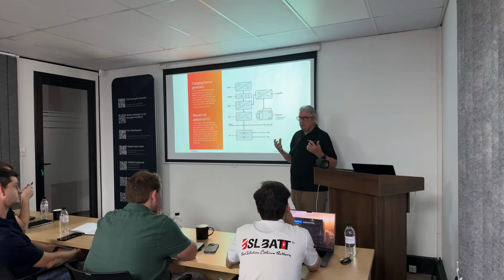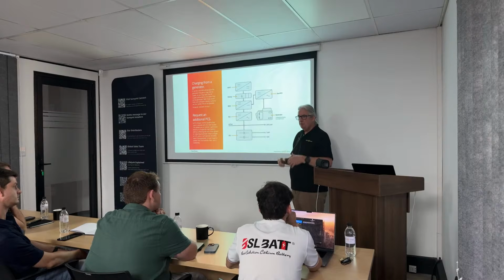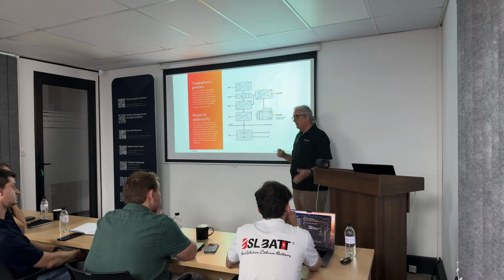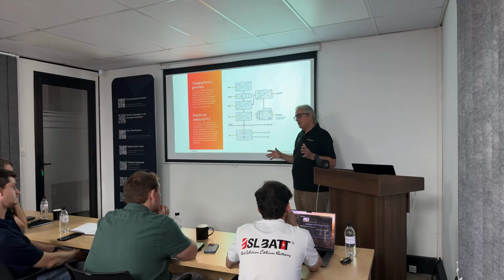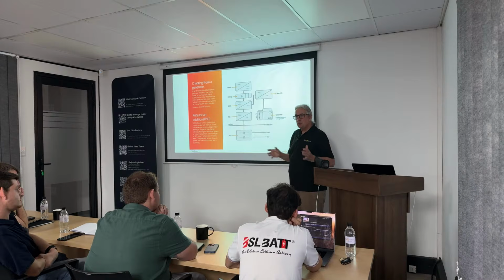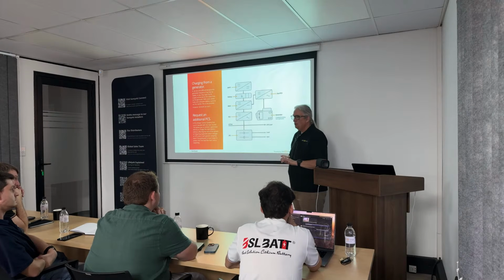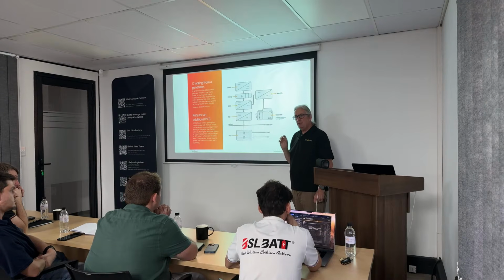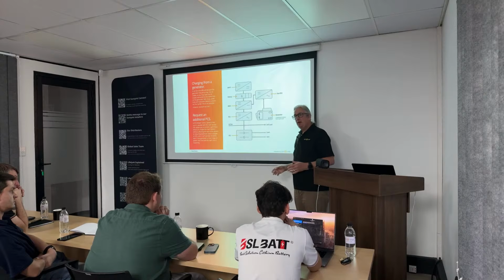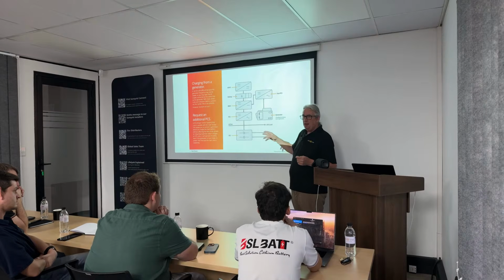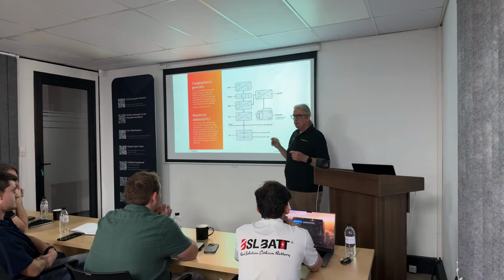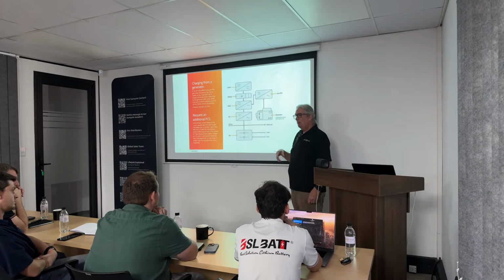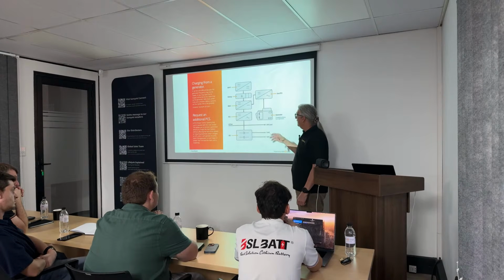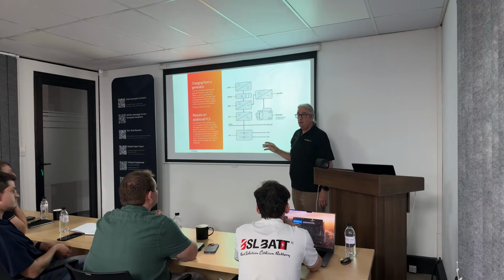I'm a little bit wary with some of these inverter generators, these new designs where the engine is running much faster and the inverter slows it down. It's just basically to reduce the size of the units. In other words, you can make a bigger kilowatt generator with a smaller engine because the engine's revving faster. Some of those with electronics, you have to be careful of, because if you backfeed, you will damage the generator. If you're using a traditional generator, a nice big heavy generator, as long as the generator is big enough, I say to people, don't keep it too tight. If you've got a 1 megawatt unit, don't go and put a 500 kVA genset on it. Otherwise, you're going to get a problem, because if it backfeeds, it will damage the generator for sure. You need to make sure you're matching. Generally, if you put it on an OGS one, you can't backfeed. It will never backfeed. So it depends on how you configure it.